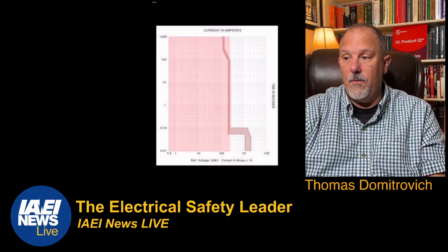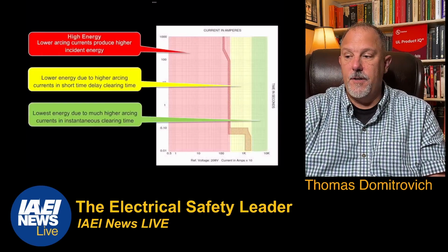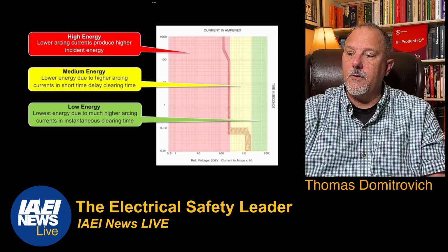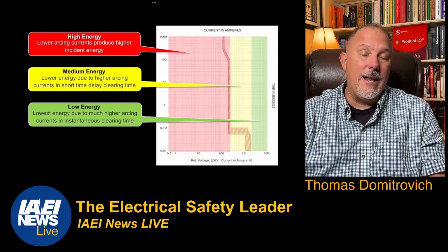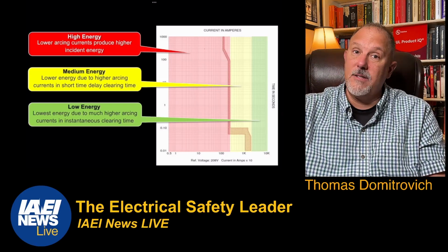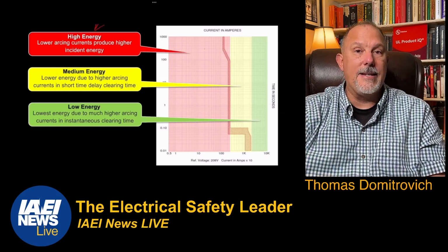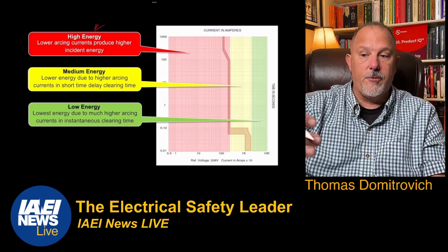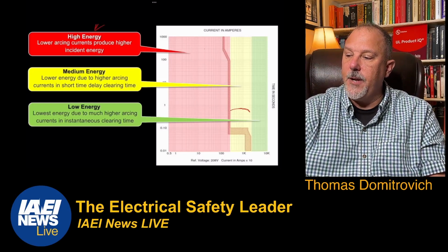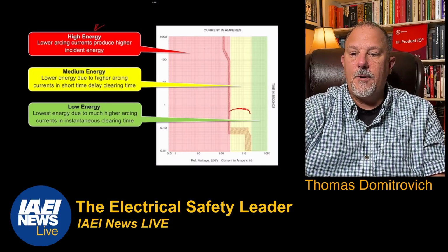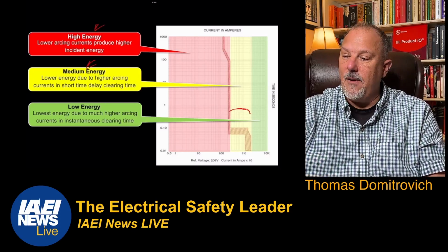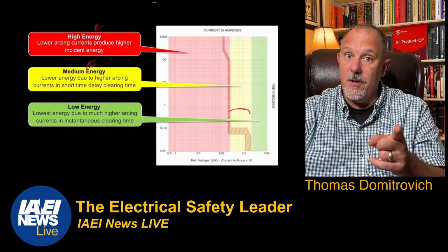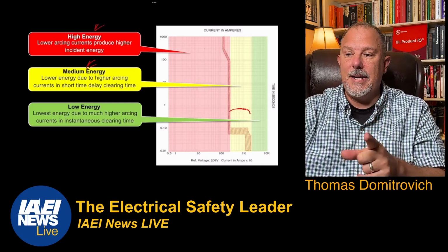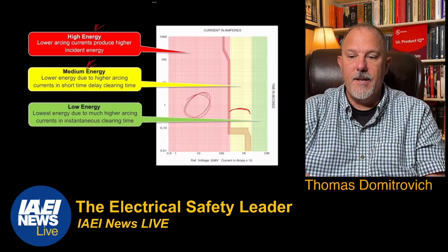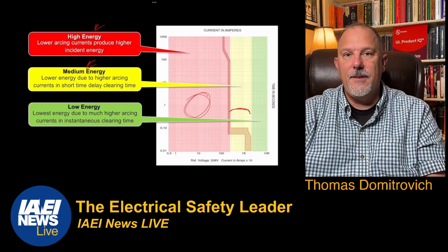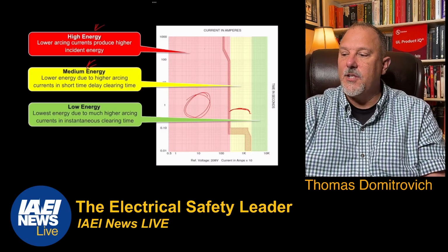So now, if you think about that trip curve, you have 3 zones. If your fault currents are low, meaning I'm going to let those fault currents flow for a very long time, you have a very high incident energy because it's low fault currents, long duration. If I'm in this mid-range right here, that's your short time delay. I'm calling that a medium energy because now I could have 0.1 seconds, which remember, that's a lot of cycles of current, but it's still less than if the fault currents were in this area here. And the lowest energy that I can get, if this is my protecting overcurrent device, is when those arcing currents are high.